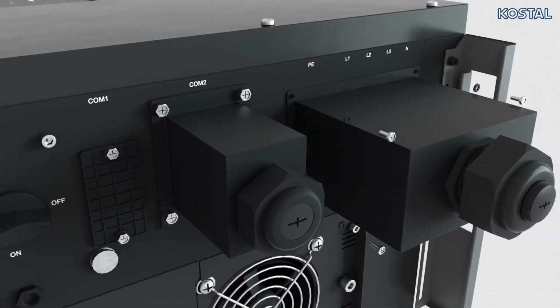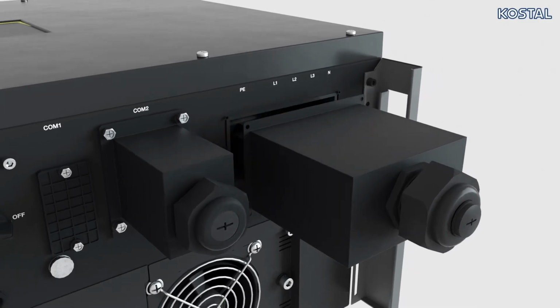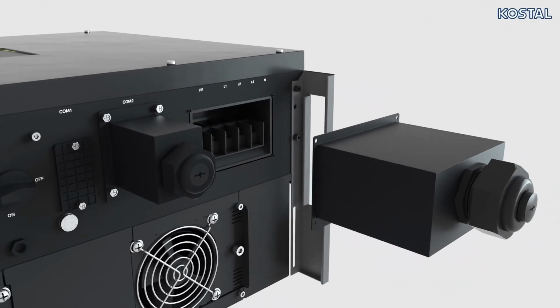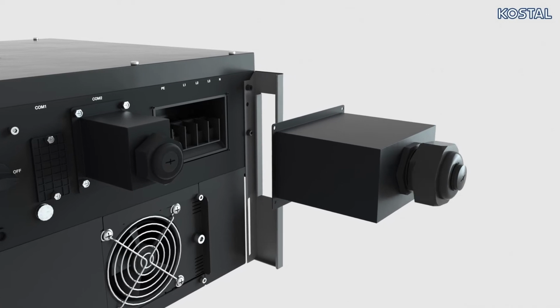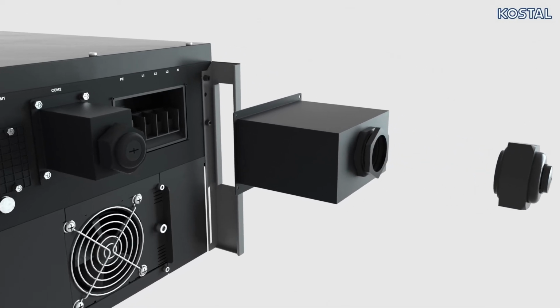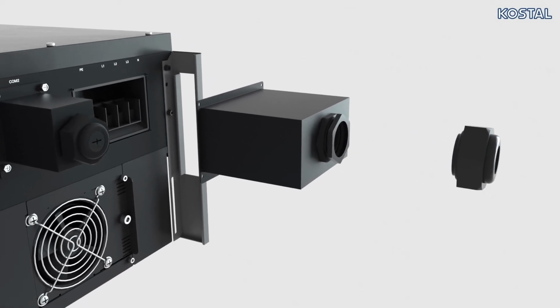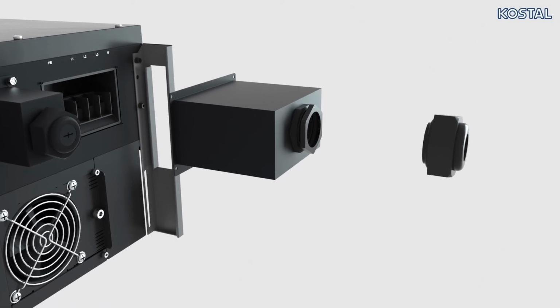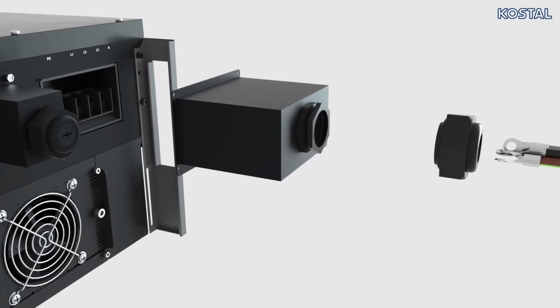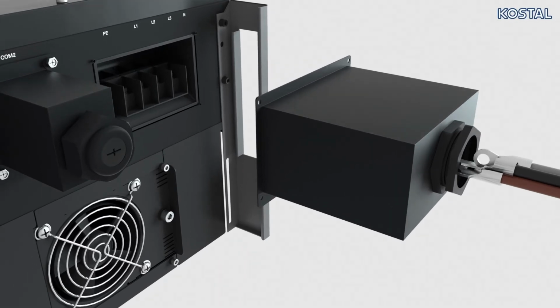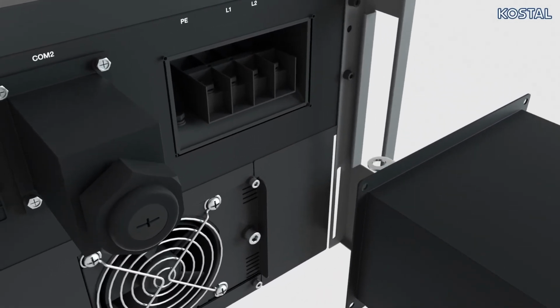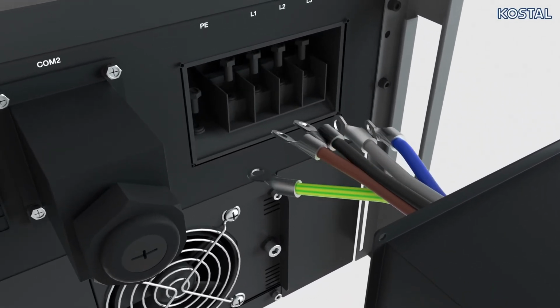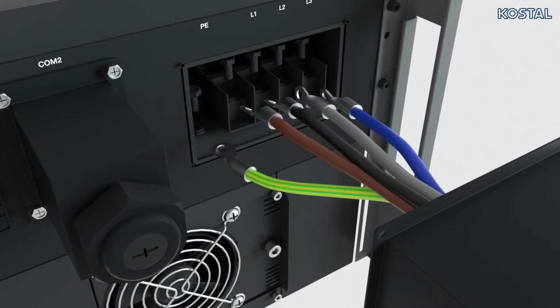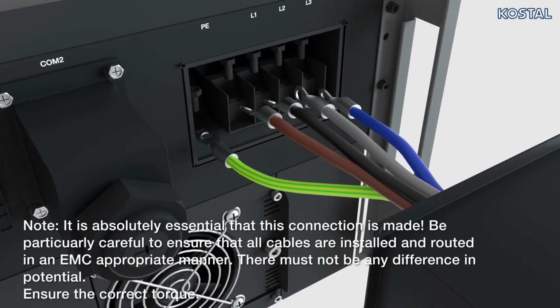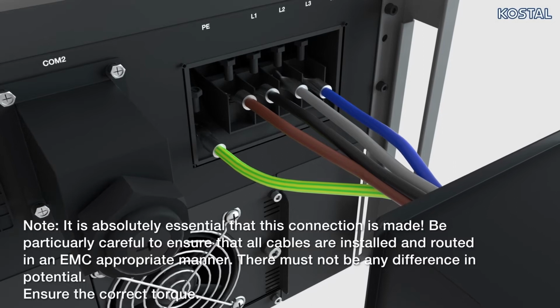Remove the connection cover screws and lead the mains cable through. Unscrew the cable gland sealing ring and press in the protective diaphragm. Guide the individual mains cable wires through the sealing ring. Use the correct ring cable lugs M6 to connect the wires to the AC connection terminal, following the labeling. Start with the PE cable.